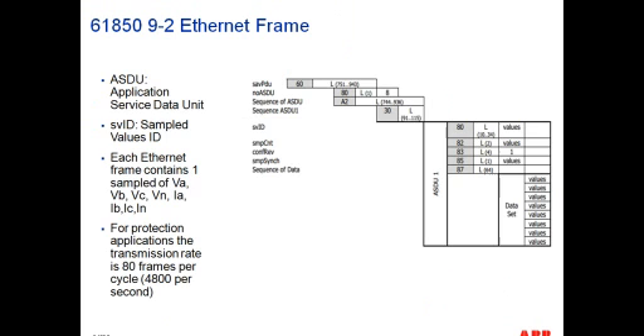That's what we see in this next slide, where inside our APDU we have an Application Service Data Unit, which includes information such as the sample values ID, the sample values identifier inside the network. This is expected to be unique so that you can identify this data stream out of your merging unit. Each data frame, and this is important, contains one sample of your phase A voltage, phase B voltage, phase C voltage, neutral voltage, phase A current, phase B current, phase C current, and neutral current. So when you look at an individual 9-2LE sample values Ethernet frame, you're going to find essentially 8 samples.